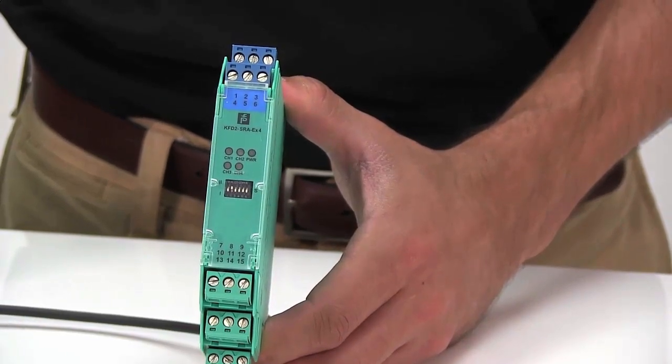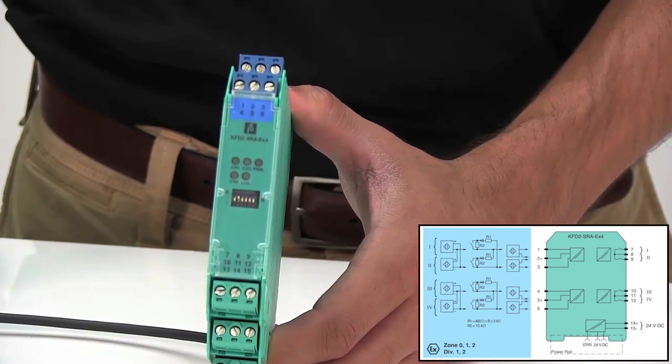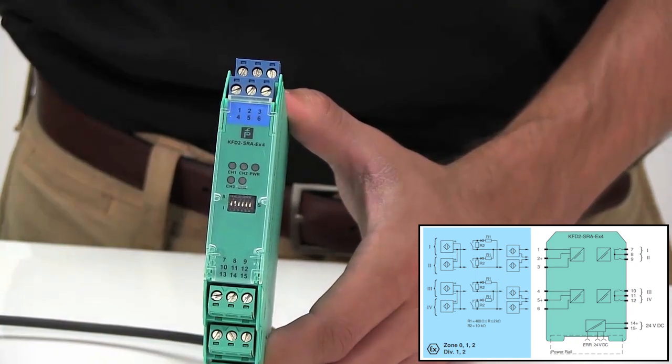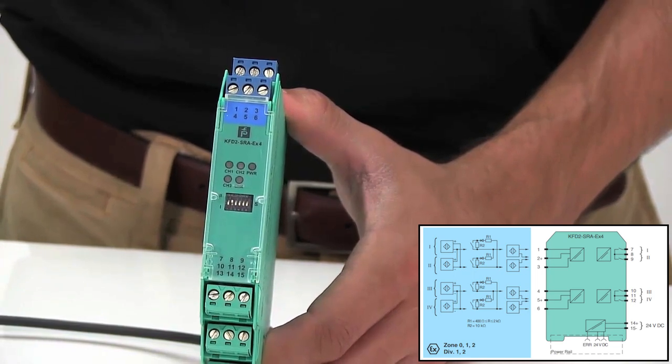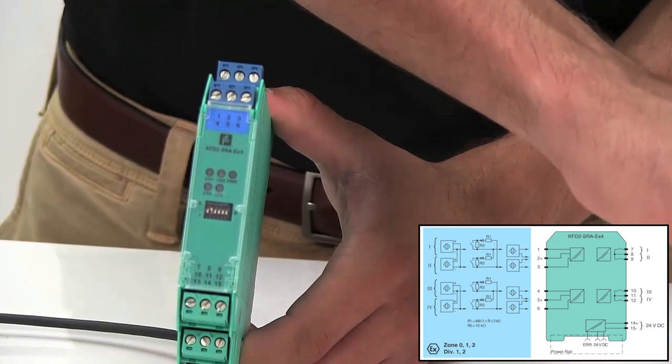To connect the NAMUR output sensor to the intrinsically safe barrier, we see that the wiring diagram of the barrier denotes terminals 2 and 1 as the positive and negative input terminals. The brown wire goes to positive terminal 2, and the blue wire goes to negative terminal 1.